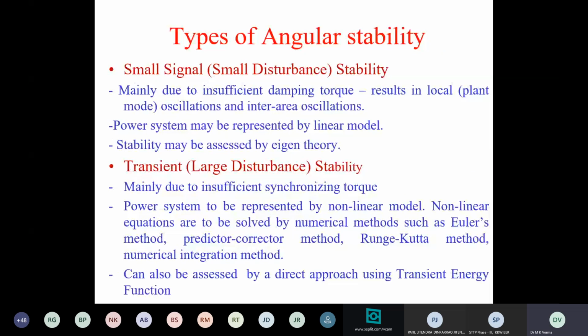Angular stability is of two types. Small disturbance stability, which is also called small signal stability, is due to small disturbance and insufficient damping torque. Since the disturbance is small, changes are small, so we can convert the nonlinear model into an approximate linear model, and you can use the Lyapunov first method based on eigenvalues of the system state matrix to examine stability. Transient stability is stability against large disturbance. This may be due to insufficient synchronizing torque. It can be assessed by solving the equations by numerical techniques or through the transient energy function, that is the Lyapunov second method.